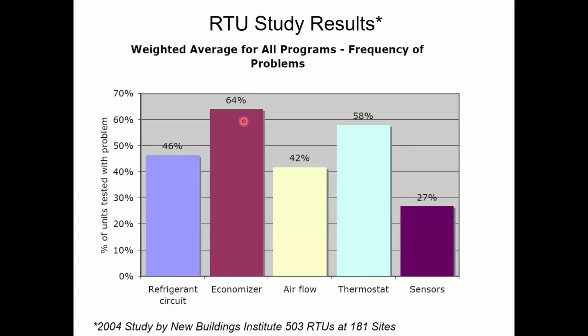Economizers, 64% of the time something was jacked up. There's a more recent Honeywell study that has about 70%. By the way, Honeywell makes the vast majority of economizer controllers in the market, and their own study says 70% of them are jacked up in the field. But this one was 64% were jacked up. That means the economizers are either propped open, or the economizer is screwed shut, or the economizer has the wrong set points, or the actuator is turning but it's laying on the ground instead of being on the shaft. All kinds of things can go wrong with that, and we'll circle back to that in a little bit when we talk about economizers here.